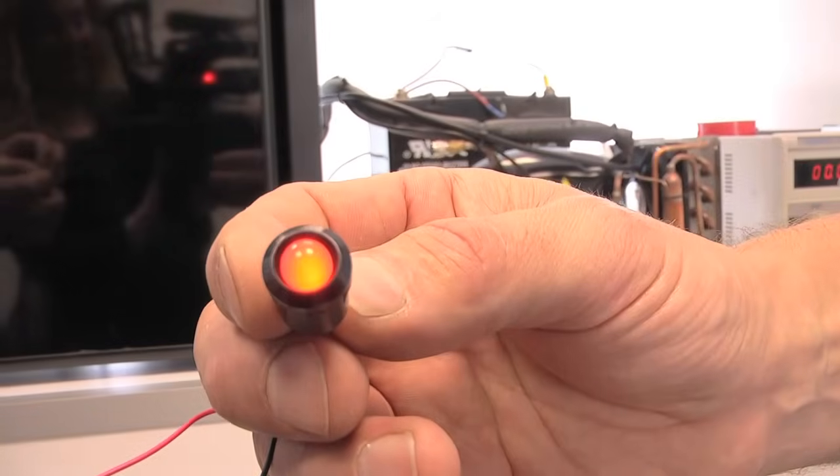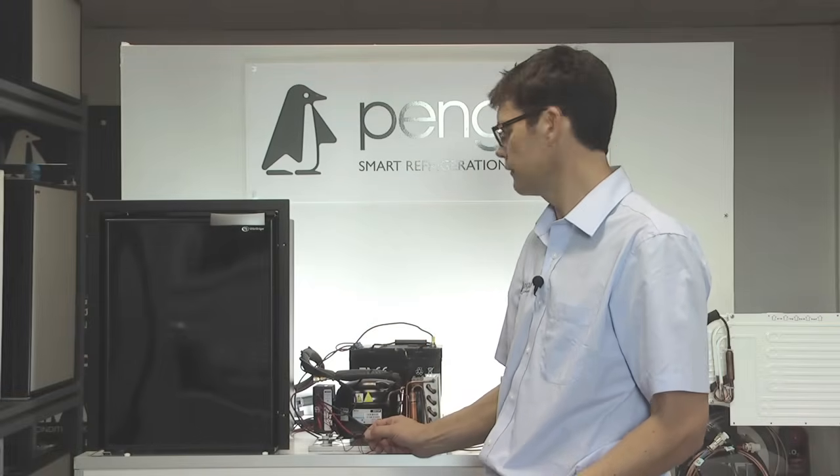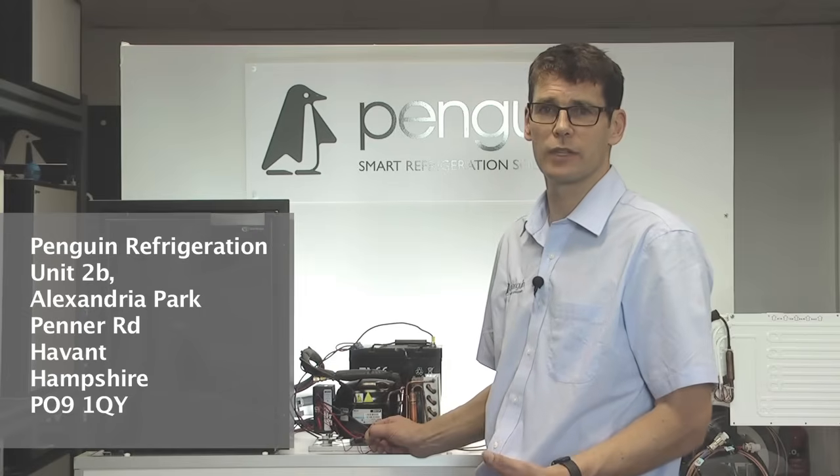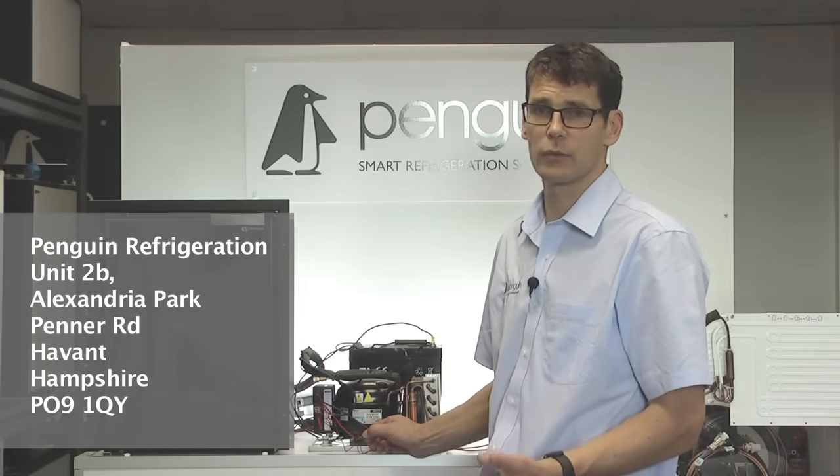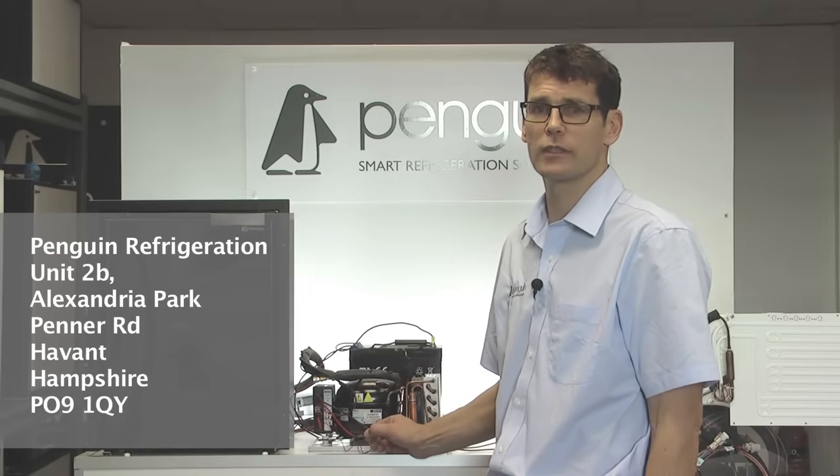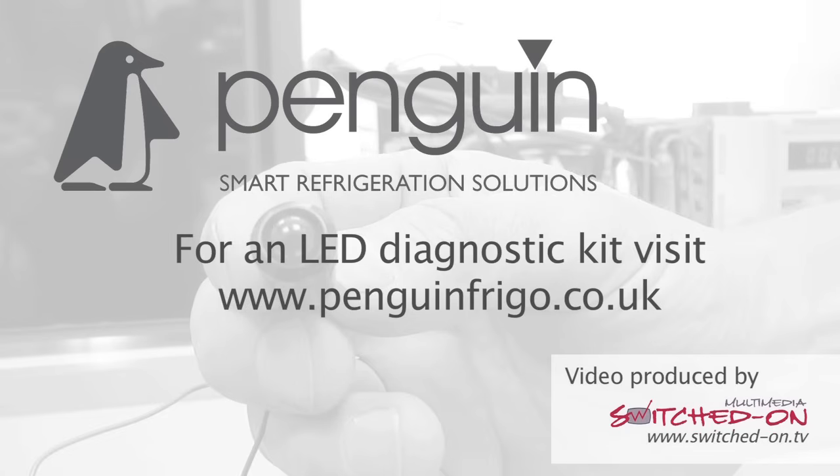We're not going to demonstrate fault codes 4 and 5, because they both relate to either a failed controller or an issue with the refrigerant. And what we would generally suggest, if you are getting fault codes 4 or 5, would be to take the controller off and post it back to us. We can then replicate the test, and if we get the same results, it's a new controller. If we don't, that would suggest that perhaps there's something at fault with your refrigerant system, and you would need to call in a refrigeration engineer.